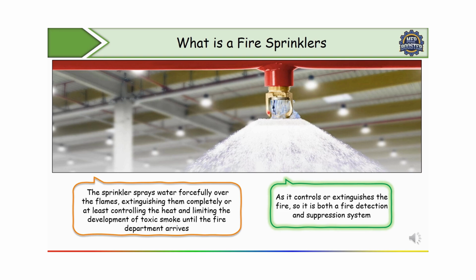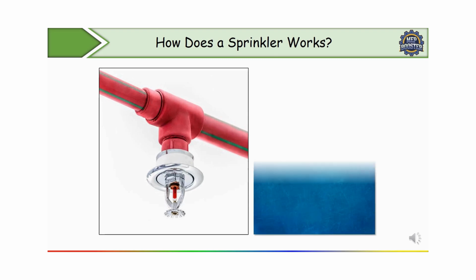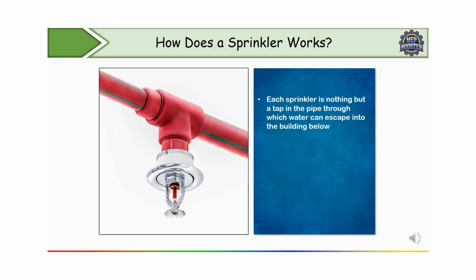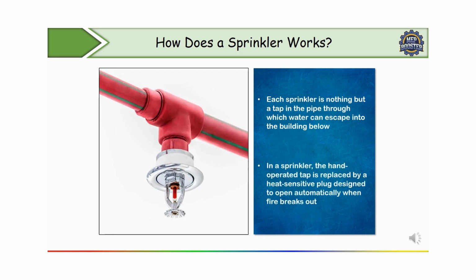So this is the device. The sprinkler head is the device that releases water when a fire is detected, and sprinklers are typically mounted on the ceiling or wall. There are various types of sprinkler head, including pendant, upright, side wall, and concealed type, etc. We'll discuss that; we have a separate topic for it. Now the question is, how does a sprinkler work? Each sprinkler is nothing but a tap in the pipe through which water can escape into the building below. In a sprinkler, the hand operated tap is replaced by a heat sensitive plug designed to open automatically when fire breaks out.